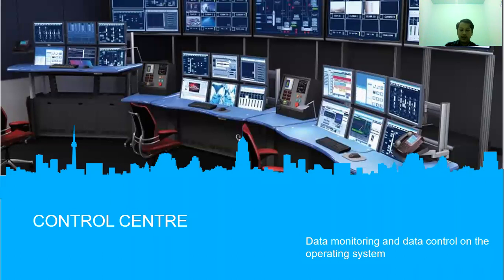Here is a control center. A control center is where the control of the electrical power system is located. We can monitor data and control data within the operating system. At the control center, there is a monitor that displays electrical power network diagrams that can show the condition of the process in the field or the state of the equipment integrated in the system. At the control center, the dispatcher is able to perform remote controlling of the equipment in the field that can be monitored or taking the necessary data. So you can control the equipment in the distant place from control center.